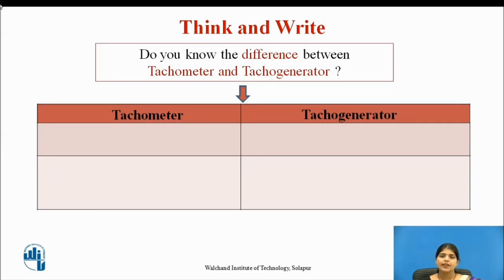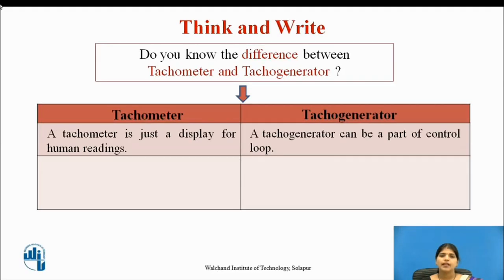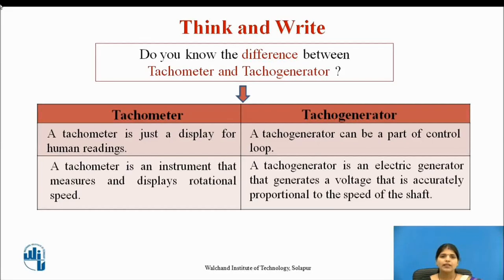Let us see the difference between tachometer and tachogenerator. A tachometer consists of a tachogenerator, and a tachogenerator is usually referred to as a permanent magnet DC brush generator. A tachometer is just a display for human readings, while a tachogenerator can be a part of a control loop. A tachometer is an instrument that measures and displays rotational speed, but a tachogenerator is an electric generator that generates a voltage that is accurately proportional to the speed of the shaft.